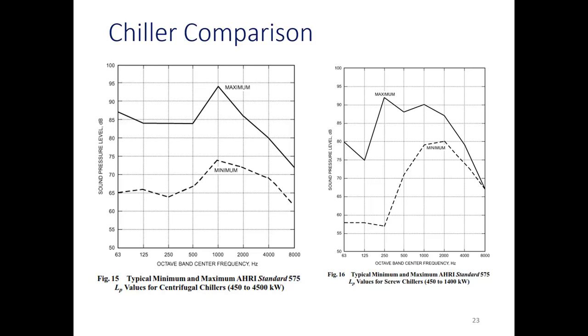Here we have a chiller comparison: centrifugal chillers and screw chillers. One thing to show here is the difference between the centrifugal and the screw chillers. I tried to scale these so they're fairly close to the line, lining up. But you can see the centrifugal chillers produce quite a bit more noise. They have a max here at 1,000 of 94, where this one has a max down here. That's only a couple decibels less, but we're a lot more sensitive out here than we are here.